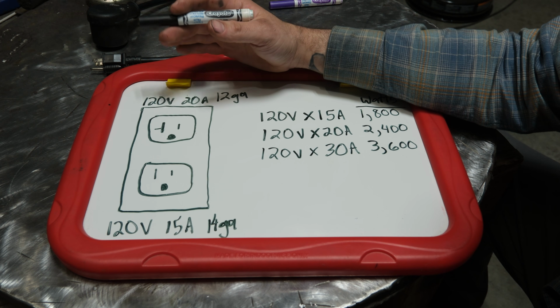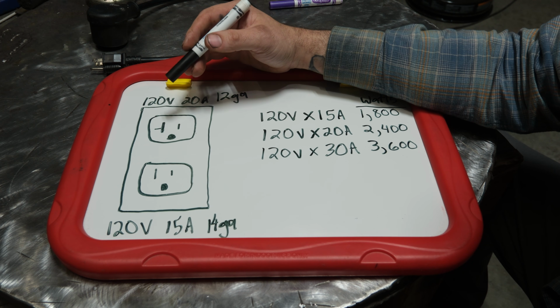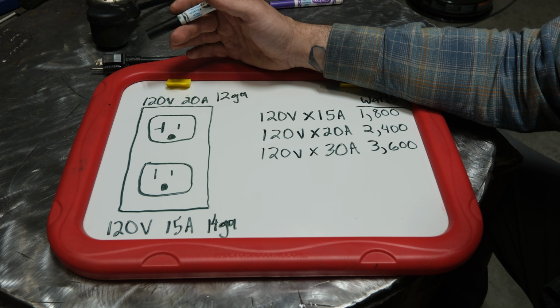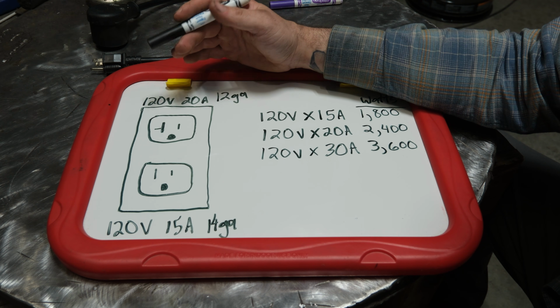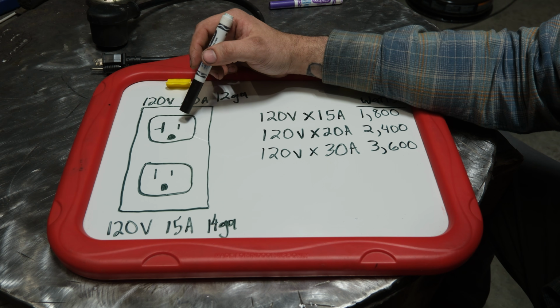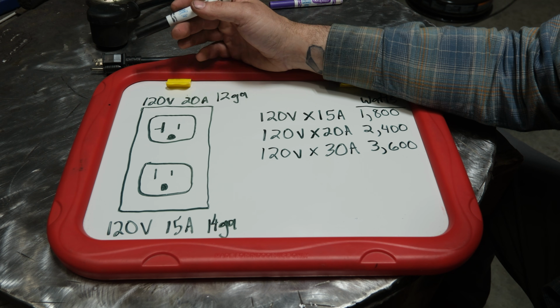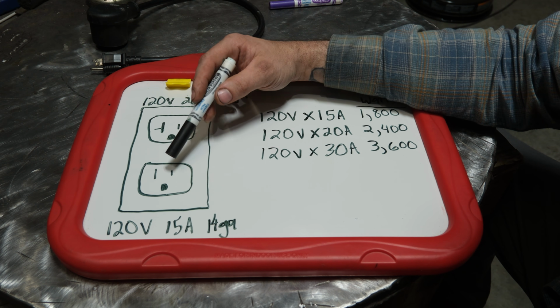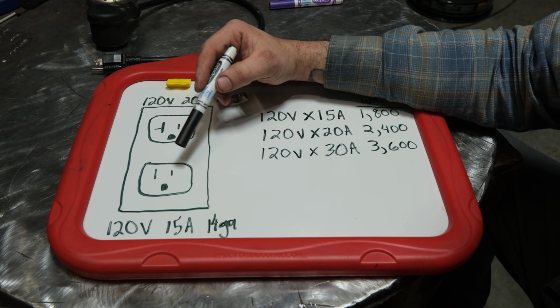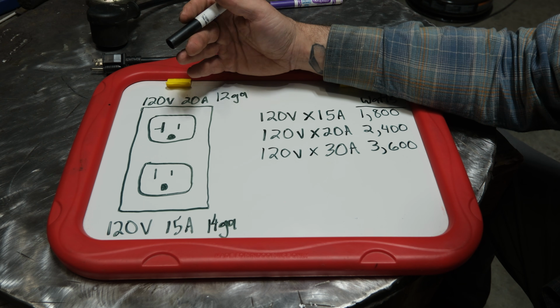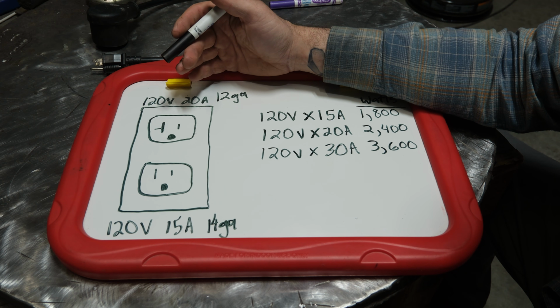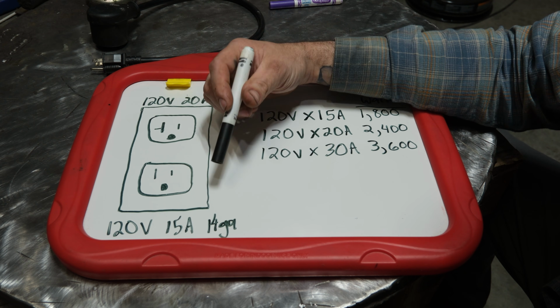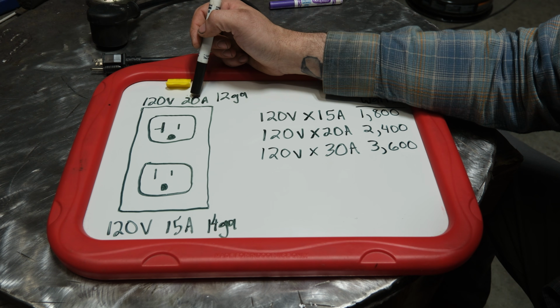Sometimes you just gotta accept that a lot of things aren't really what I would consider being code legal, but it is what it is. So anyways, the point of what I'm making here is, if you have the sideways prong, you got a 20 amp circuit. If you have straight up and down prongs for your outlet, you need to look at the breaker that's hooked to that and see if you have a 15 amp rated or a 20 amp.